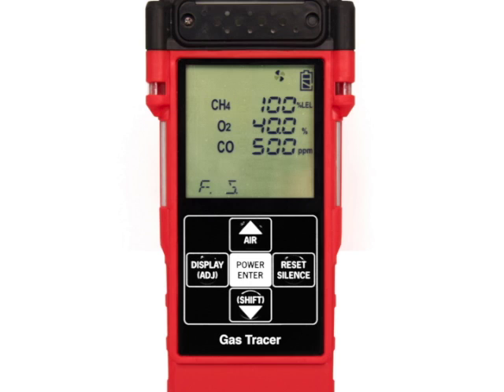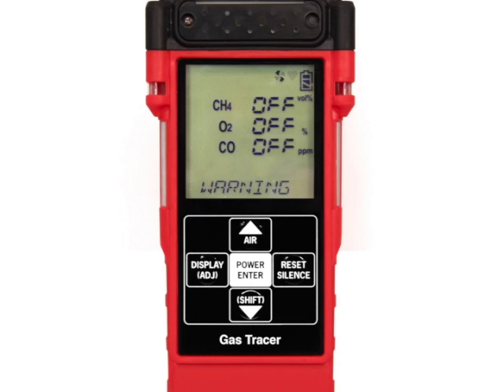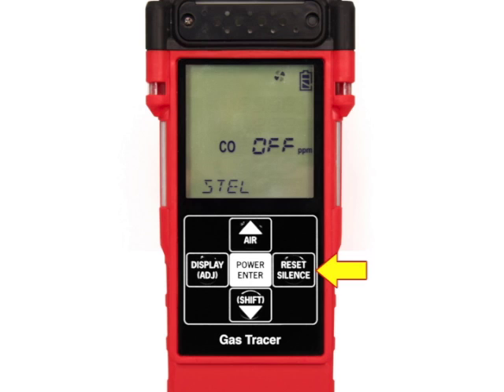The remaining screens are only displayed for about a second each. You will see the full-scale values for each channel, the low alarm point for each channel, the high alarm point for each channel, followed by the STEL and TWA set points for carbon monoxide. If the HC range is set to percent volume only, you will have to press and release the Reset Silence button for each of these screens to acknowledge that there are no alarms when the unit is operated in that fashion.